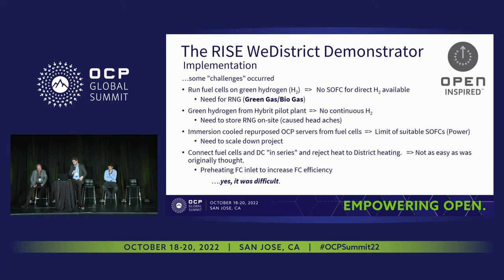The idea was to boost the temperature of the heat coming out of the immersion cooling system and use the hot water from it to cool the fuel cells, boosting their temperature. But that wasn't easy either, matching flow rates and so on. So we ended up using heat from the fuel cell and the data center to preheat the air for the fuel cell instead. We ran into a lot of problems before we got things up and running.